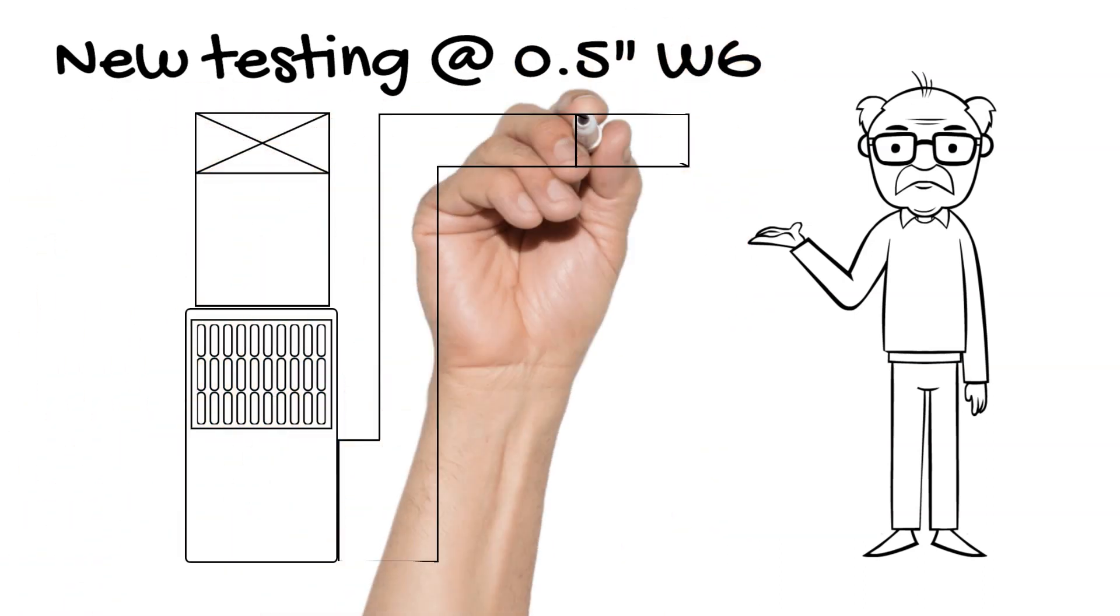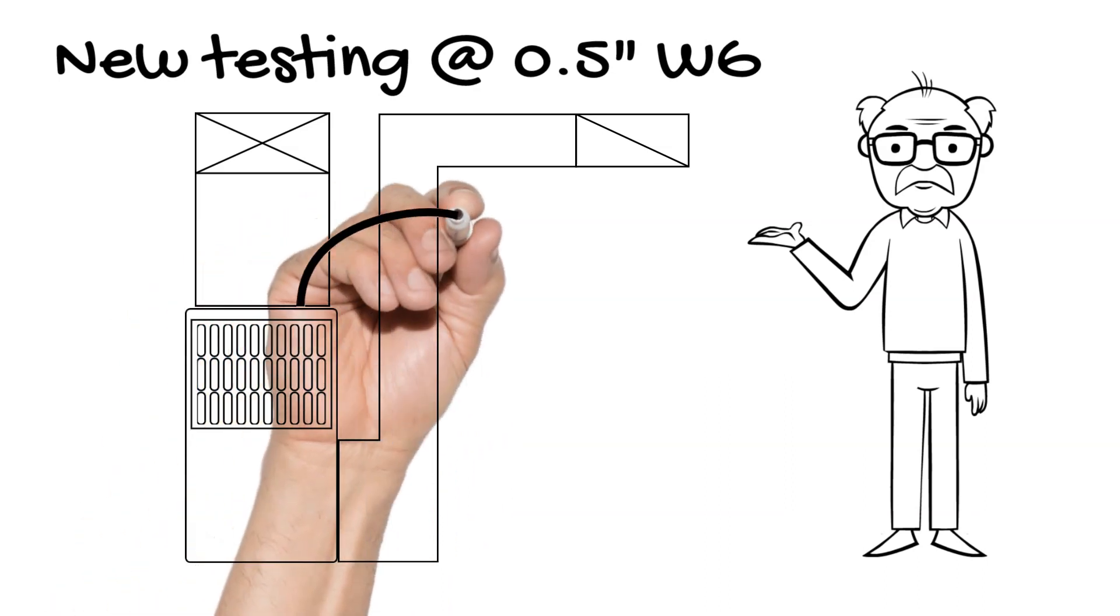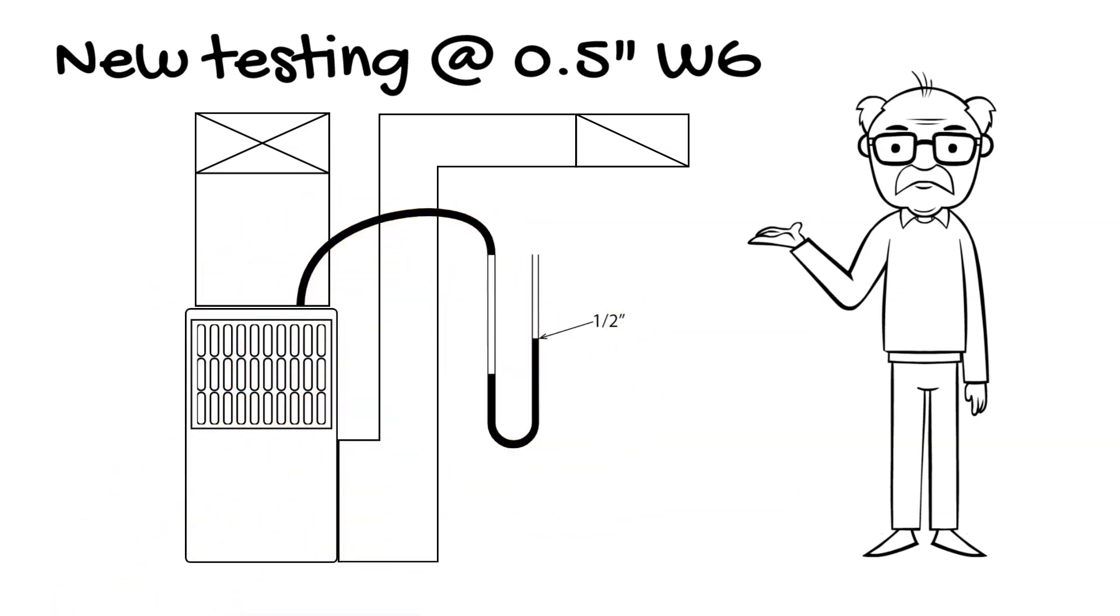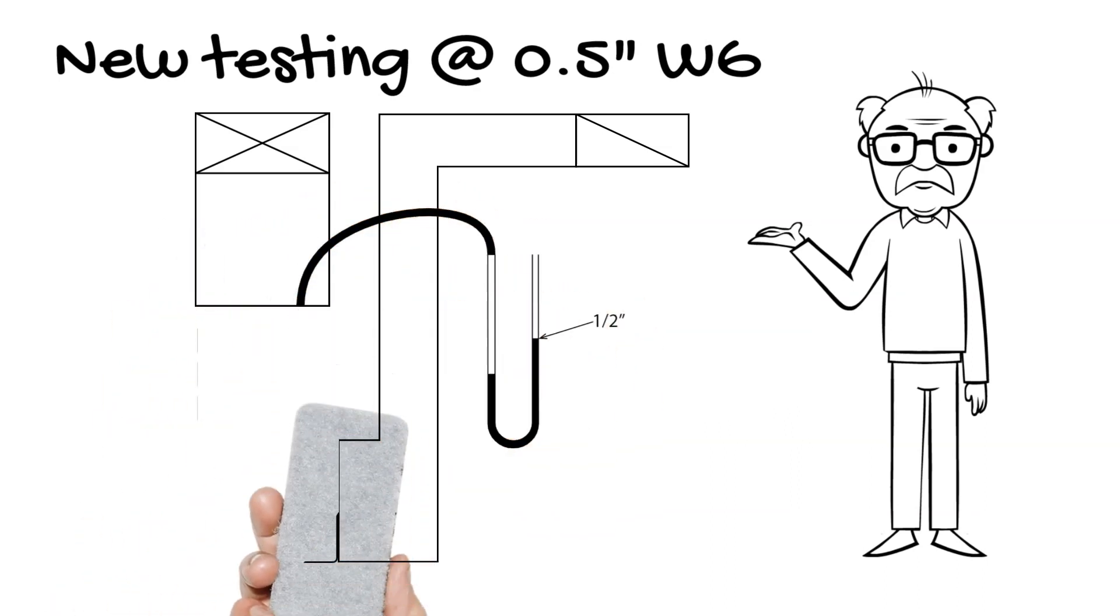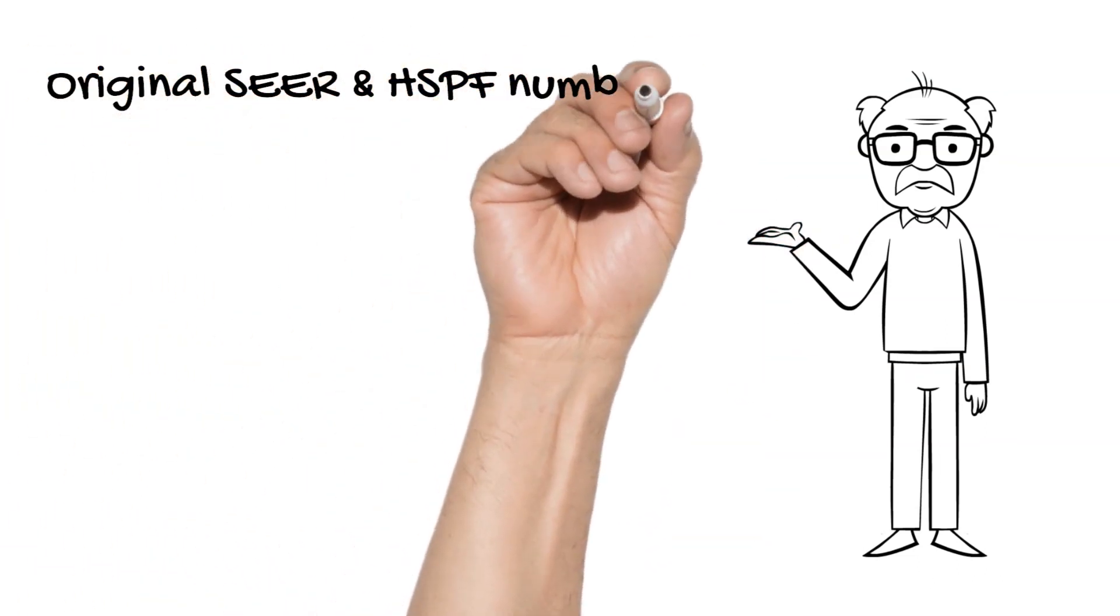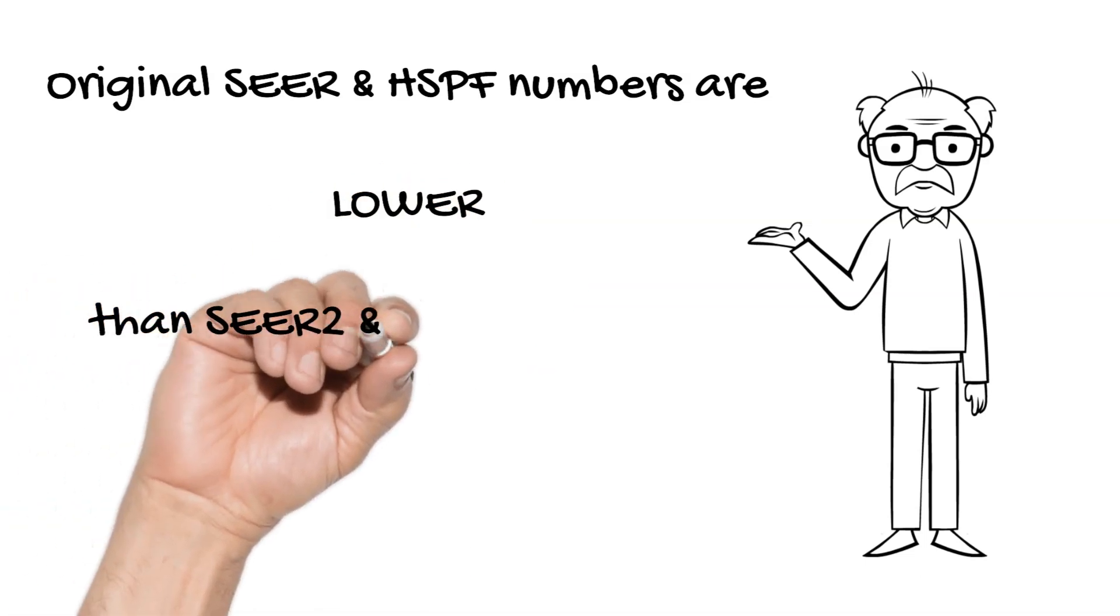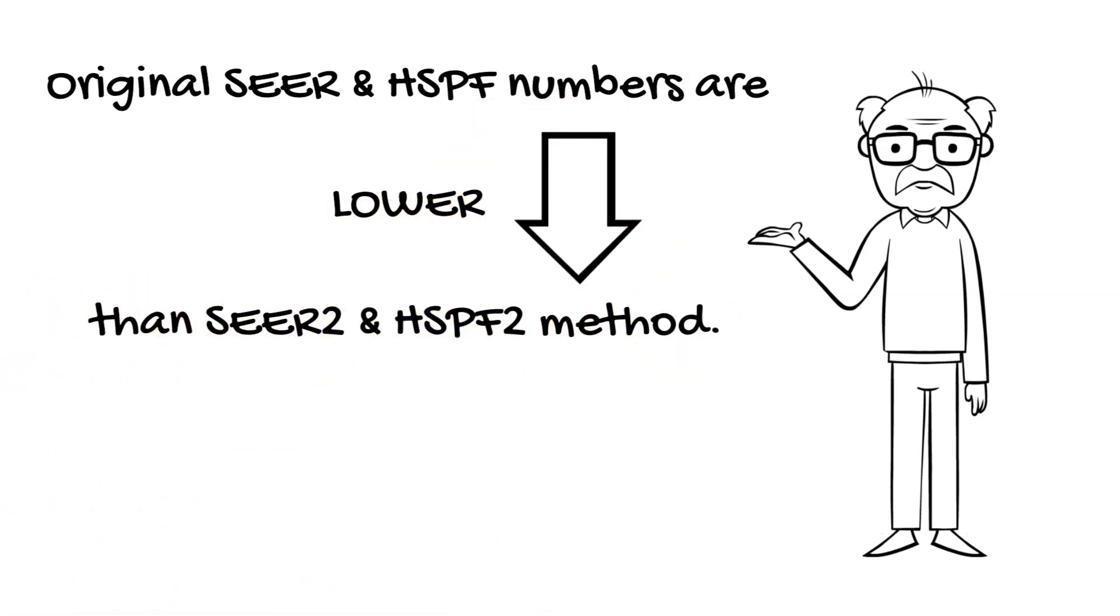The new testing procedure is performed at 0.5 inches water column. Thus, the results are in line with the more typical home conditions. That also means the old SEER or HSPF numbers would be calculated lower as SEER2 or HSPF2 values.